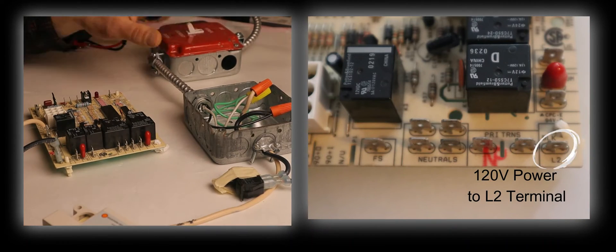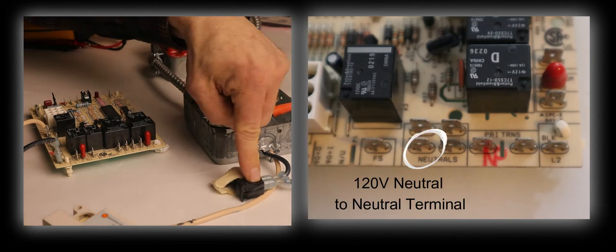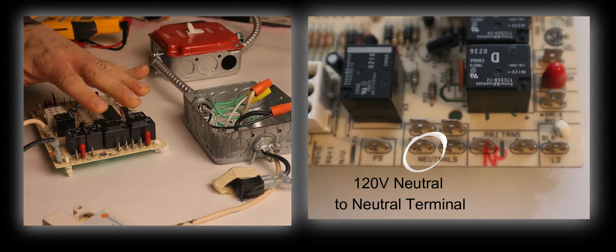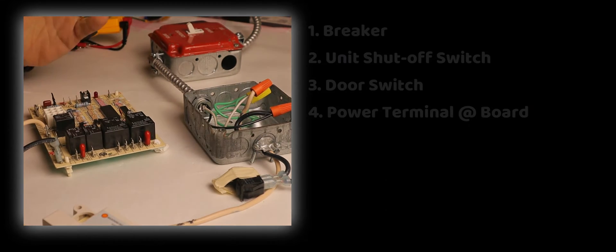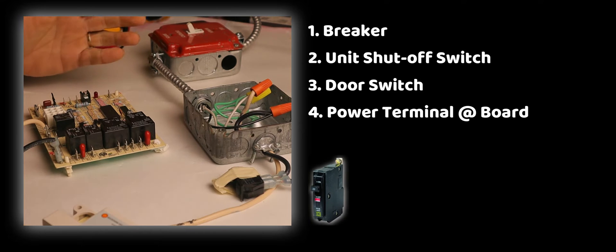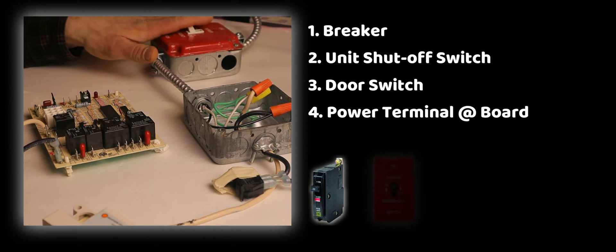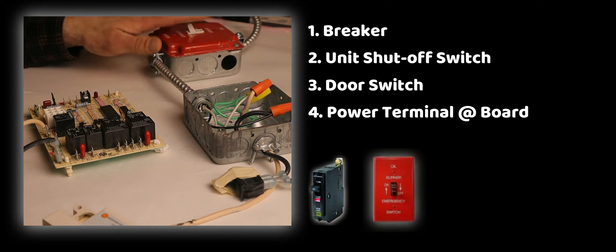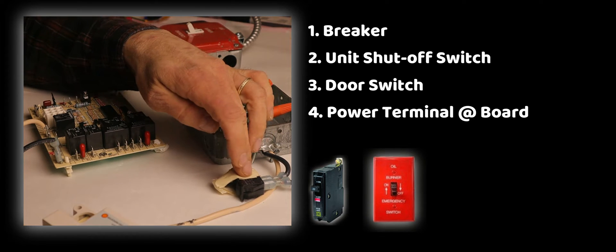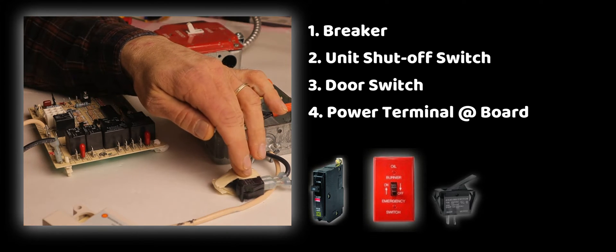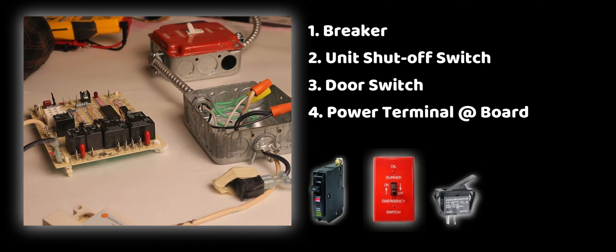Here we have a burner shutoff switch, a junction box, a door switch for a furnace, and a control board. We already have a list going now. Our first source is the breaker all the way back to the electrical panel, that's point one. Our burner shutoff switch is point number two. Power goes through there, power goes through our door switch, that's point number three, and now it comes into our control board.